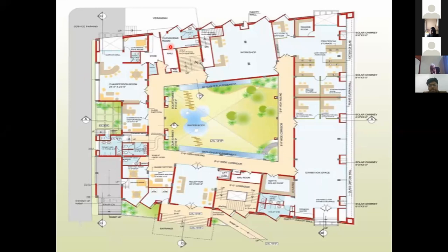And interesting, if you see the windows, the east and west facade has high radiation of sun coming in and huge glare, so it is made sure that the windows are tilted towards the south side. So you have ample daylight, but no glare at all. And also making sure that all your east and west facades have services so that your heat gain, if there is any within the building, is limited to these service areas and is not coming into your comfort zones. So your staircases, your toilets, your reception areas, which are least-used spaces, are placed on the east and west facade. A very good example.